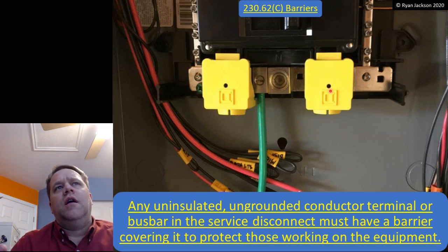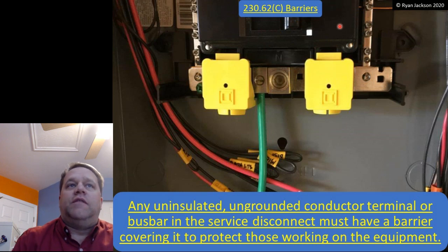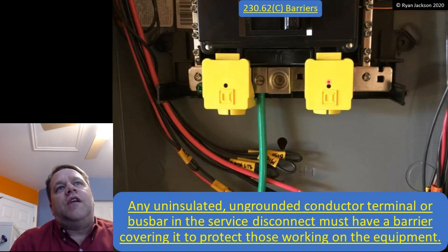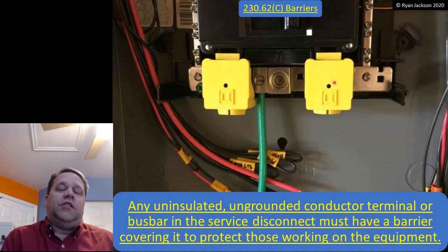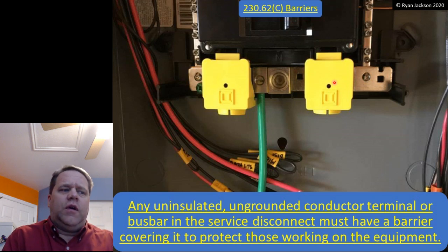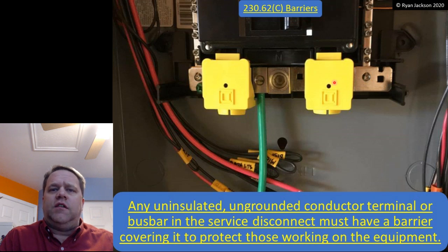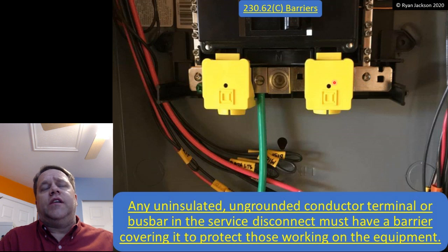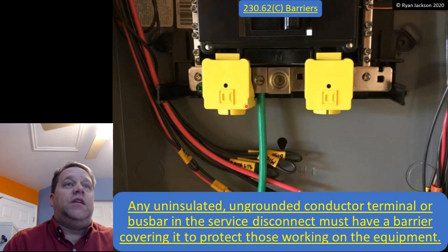The idea here is if I have to work on this panel board, I shut off the breaker. The panel board itself is de-energized, and everything downstream of it is de-energized, except for these two lugs that are staring me in the face. The only way I can de-energize those is to call the utility and get a scheduled outage. So in order to comply with OSHA and NFPA 70E requirements for safe work practices, I would actually have to call the utility and schedule an outage anytime I had to do anything in this panel.